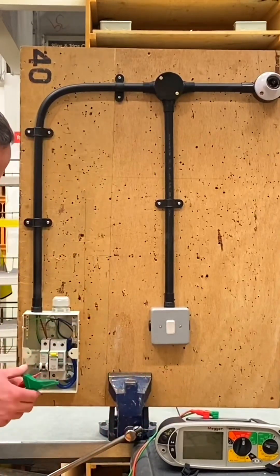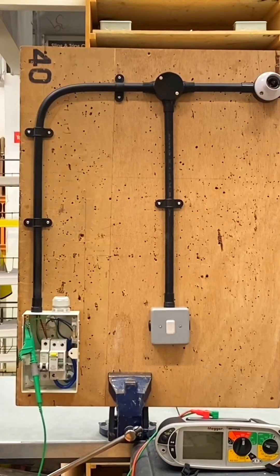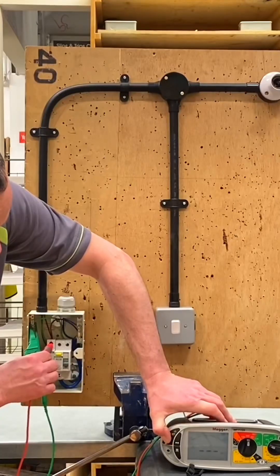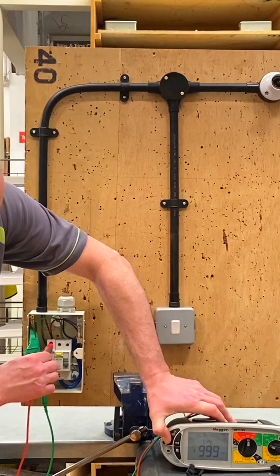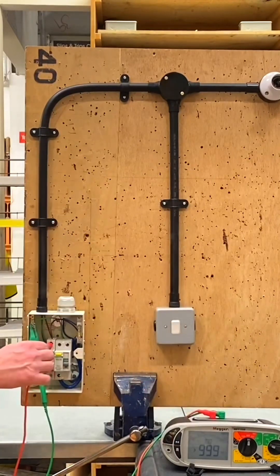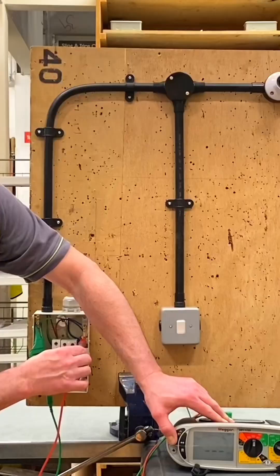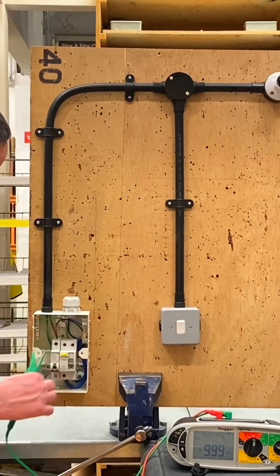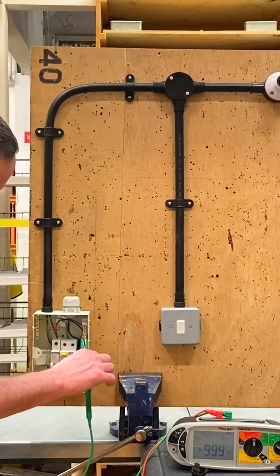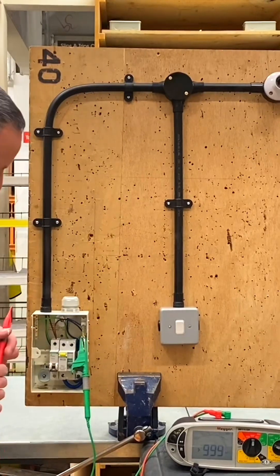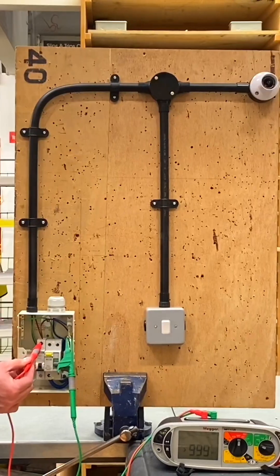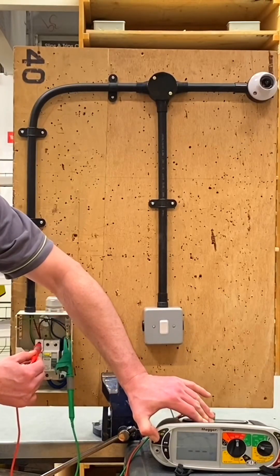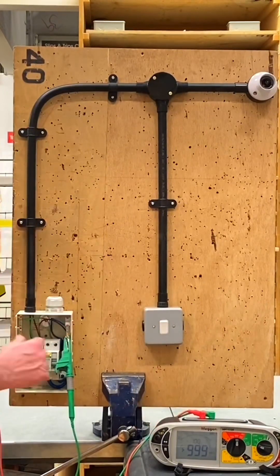Switches on, covers on, RCCB off, breaker off, set to the appropriate scale on our instrument, and we're ready to go. First, I'm connecting onto the earth bar and on the top of the breaker. We press and hold our button and our reading is greater than 999 mega ohms. We go on to the neutral bar and our reading is greater than 999 mega ohms. We move our crocodile clip across to the neutral bar, onto the top of the breaker where the line conductor is. We do line and neutral next, press and hold, and that's our insulation resistance test completed.